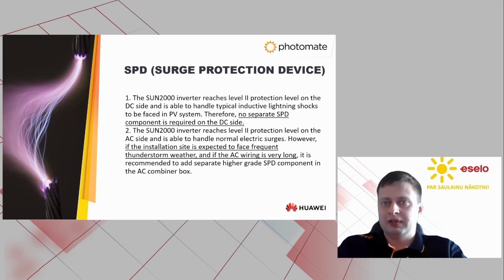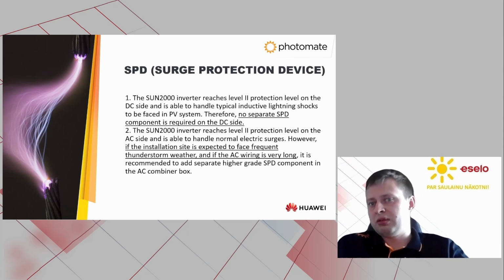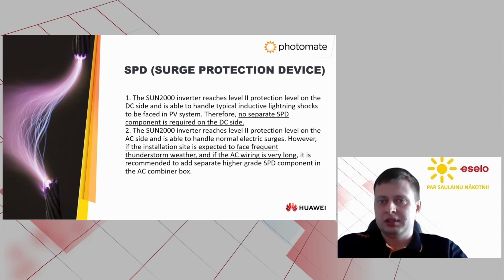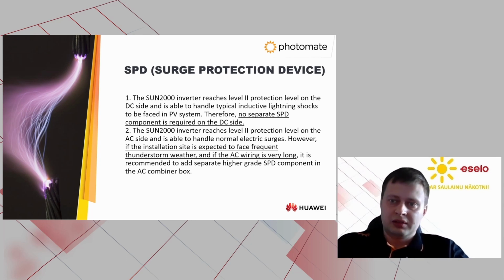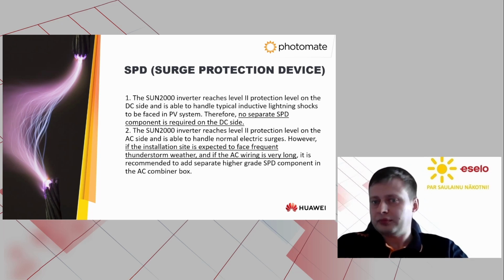So the Sun 2000 inverters are designed to provide a high level of protection against lightning and electrical surges on both sides, so it means on the DC and AC sides. Specifically, the inverter achieves a level 2 protection rating on the DC side, which allows it to effectively handle typical inductive lightning shocks that may be encountered in the system. As a result, it is not necessary to install a separate surge protection device on the DC side. On the AC side, an SPD type 2 is also installed, but if there are long lines supplying the inverter, it is better to have an additional SPD with a higher grade installed in the AC combiner.